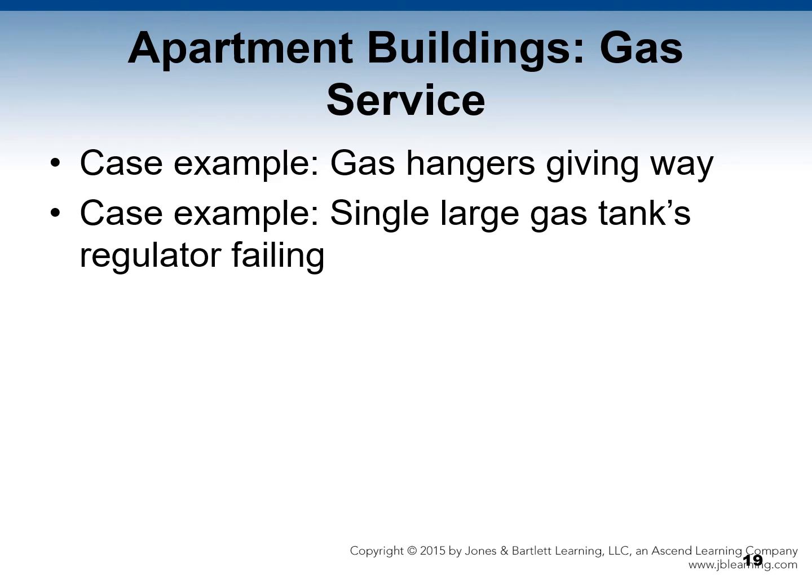Where there is no utility gas service, liquefied petroleum gas or LPG storage tanks may be used. One case example is in Anne Arundel County, Maryland, actually where I was born. Home of the U.S. Naval Academy. In Anne Arundel County, Maryland, an apartment complex was served from a single large gas tank. Its regulator failed and many fires arose simultaneously through the complex.